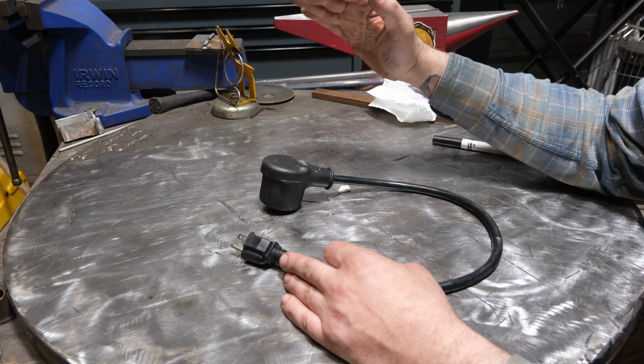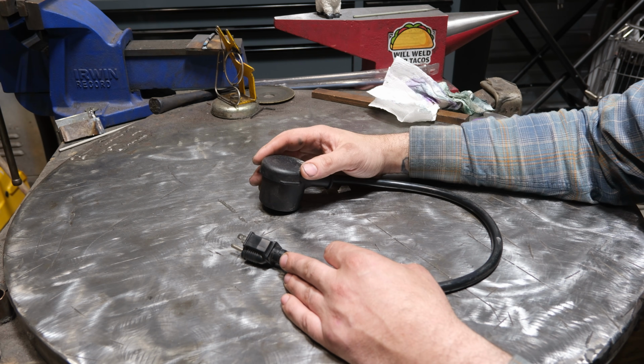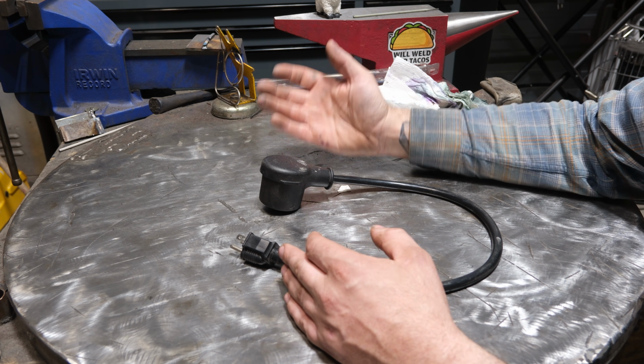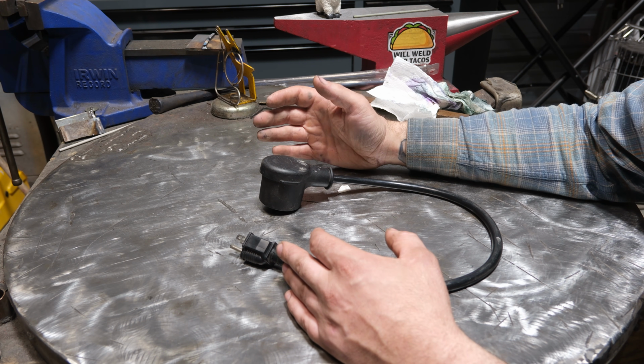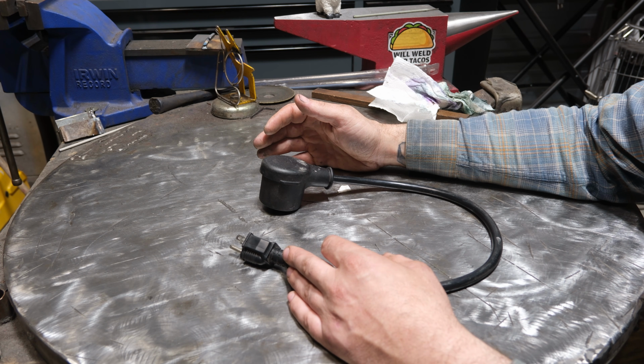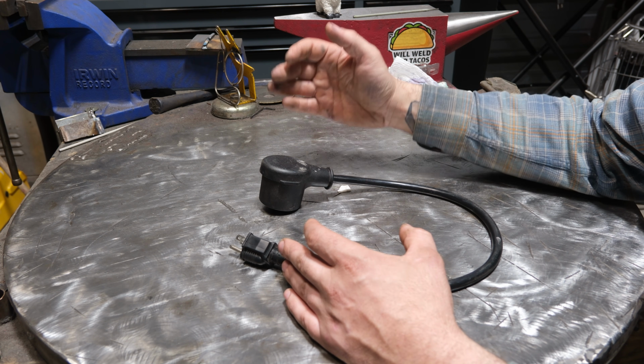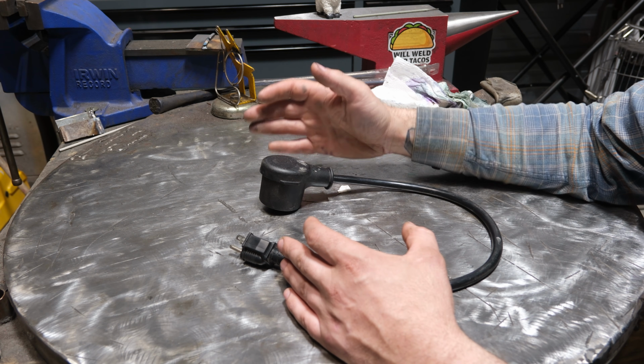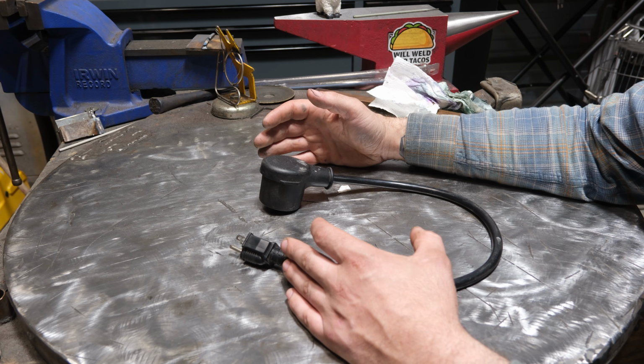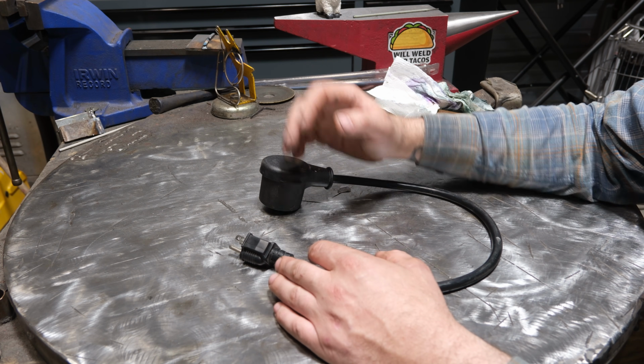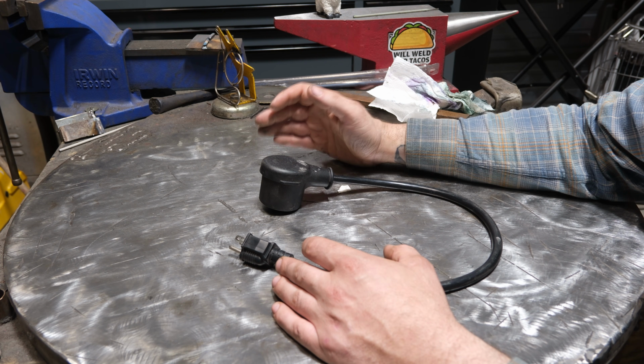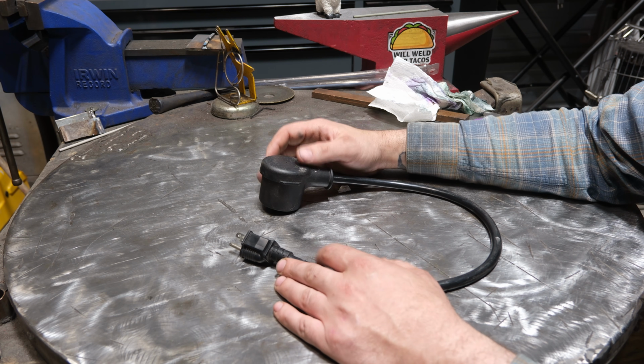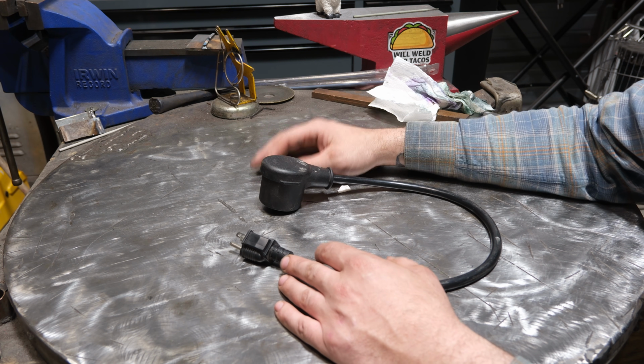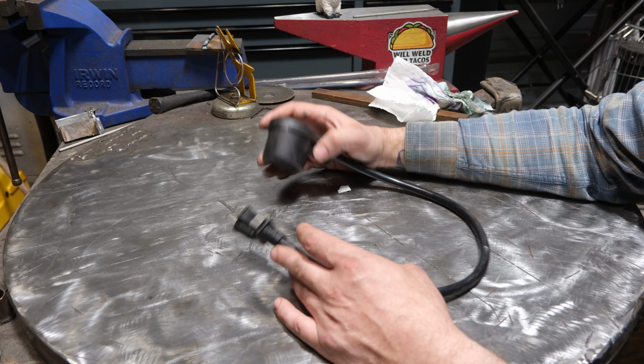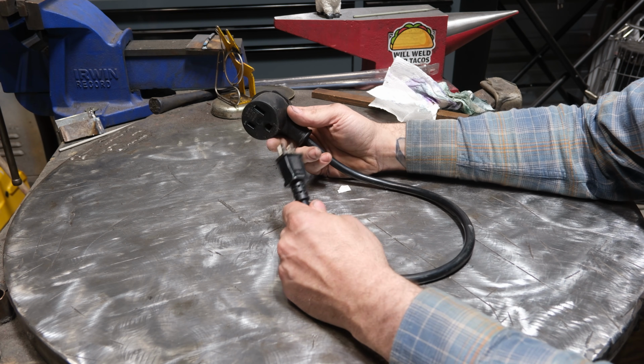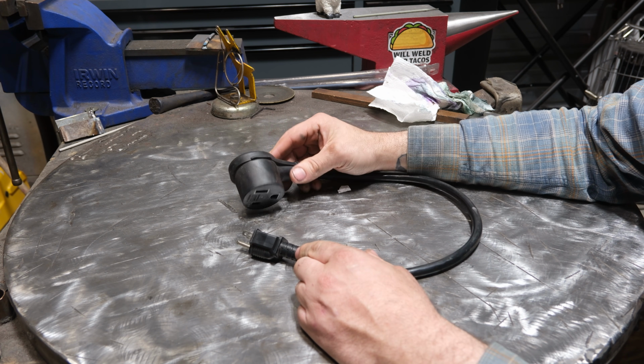And as long as you stay far enough under and you use a duty cycle, it will handle it. The problem is generators don't have that. They are not designed to let you overload particular breakers. They're designed to allow, say, you're running watts over multiple outlets, and that is how you can achieve more of what they call starting watts, because multiple circuits are loaded, but none of the single circuits are loaded to maximum. And that's the problem, is that welders load circuits to above maximum.